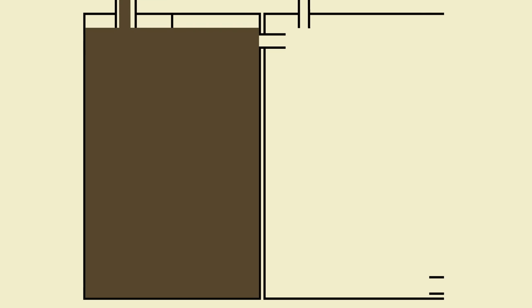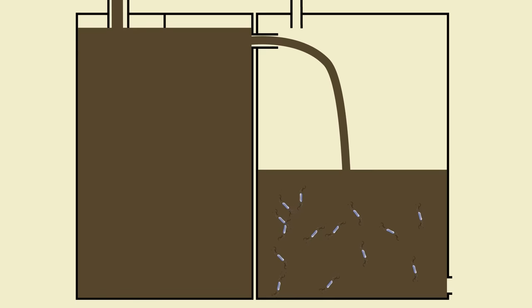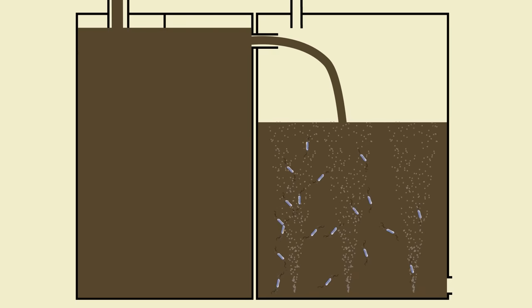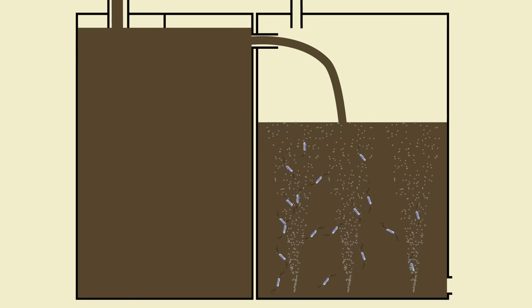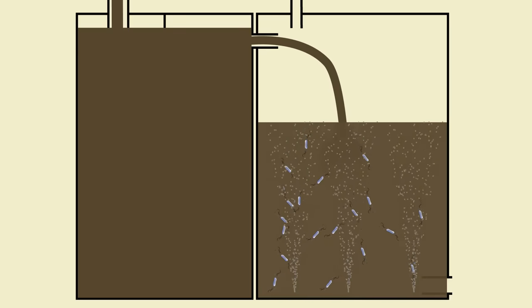From there, it passes into the next chamber — the aeration chamber. This chamber is actually filled with aerobic bacteria. Aerobic just means the bacteria needs oxygen to be able to survive. If we were to just dump all the sewage in here, the bacteria would soon use up their oxygen, so we actually use air blowers to give them a constant supply. With oxygen and the sewage as a food source, the bacteria is set to work. All this is just an accelerated form of decomposition.